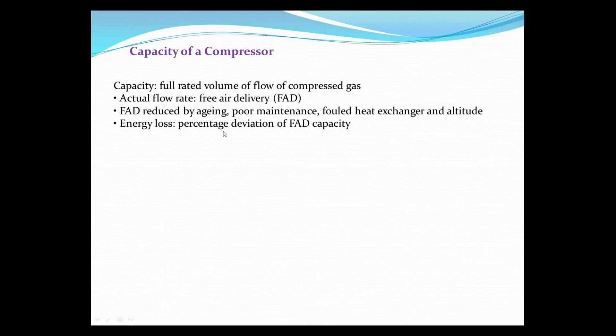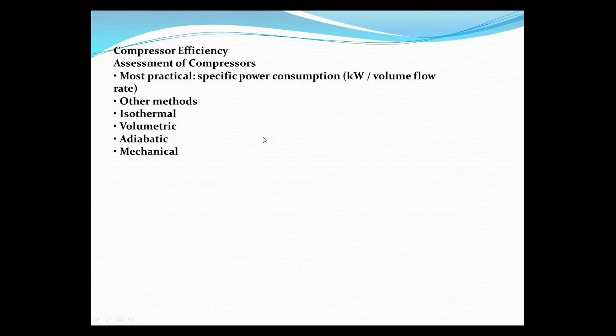Then compressor efficiency. While estimating the compressor efficiency and doing the performance assessment of the compressor, you will first, as an auditor, go for specific power consumption. In the second unit, the energy audit methodology part, you found in the 10-step methodology that the important thing about any utility, while conducting the energy audit, is to first find out the specific power consumption of that utility. For a compressor, this specific power consumption is in kilowatt per volume flow rate. You find this out first, and then you go for isothermal, volumetric, adiabatic, and mechanical efficiencies also. Clear? I think you remember these efficiencies. If not, I'll quickly throw light on these concepts in brief.